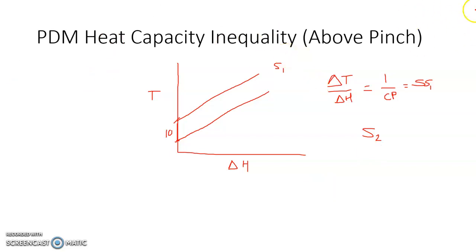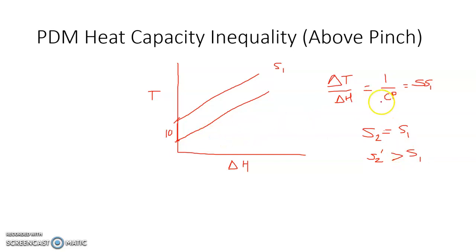Now suppose S2 dash has a heat capacity greater than S1. If CP is greater, then the slope (1/CP) is less, meaning the line tilts more toward horizontal. Starting from the pinch with a delta T of 10 degrees, the two lines diverge as energy is exchanged — the temperature difference increases. The third possibility is S2 double dash with CP less than S1, giving a steeper slope.